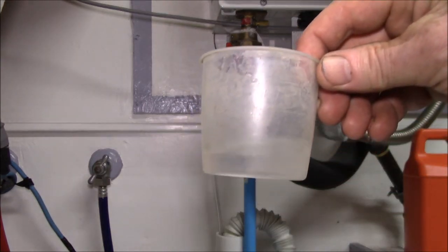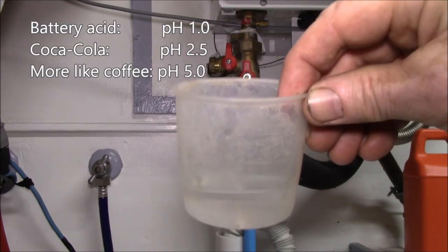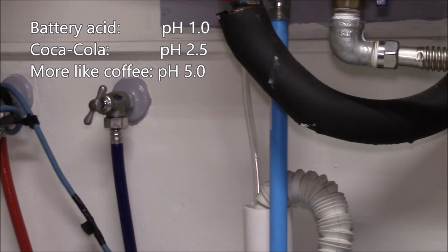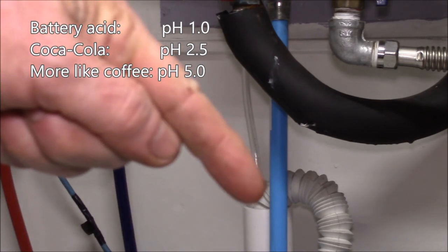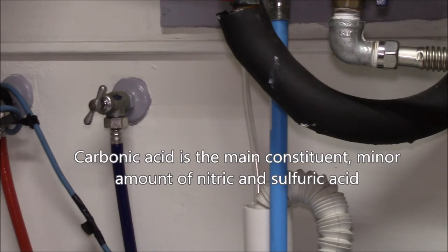That's kind of what I wanted to find out - how much water are we talking about and is this battery acid or soda pop? You're not dealing with a lot of volume, and the water that's coming out of there is really not terribly acidic. Maybe other fuels are worse.